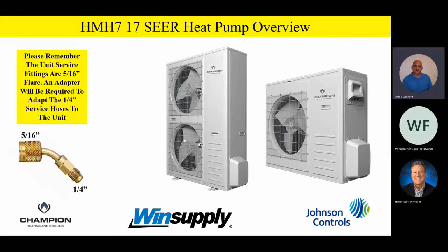Good. All right. So please remember the unit service fittings are 5/16 on the units, and you're going to need an adapter to go between that 5/16 flare fitting down to a 1/4-inch flare fitting, so you can get your service hoses on there to service the equipment. These little adapters are very common. Robinair makes them, JB makes them, several companies make them. But remind the service technicians they need a 5/16 by 1/4-inch flare adapter so they can hook their hoses up for servicing these units.